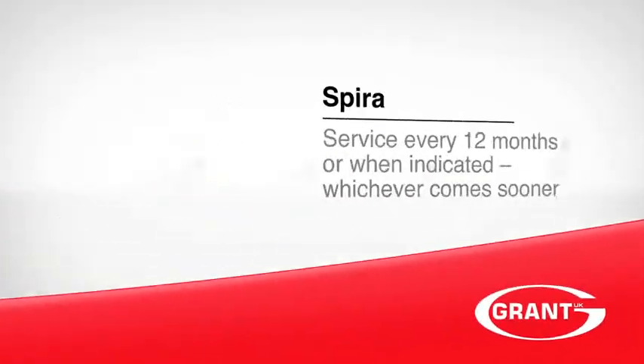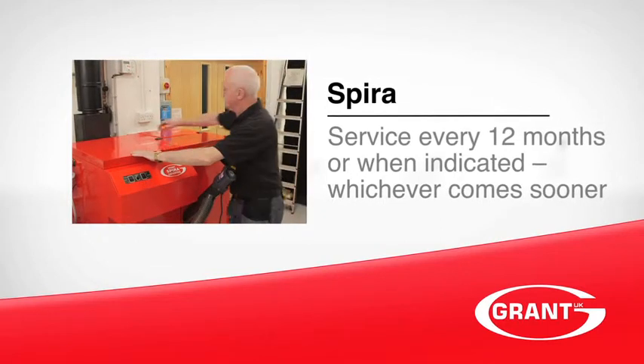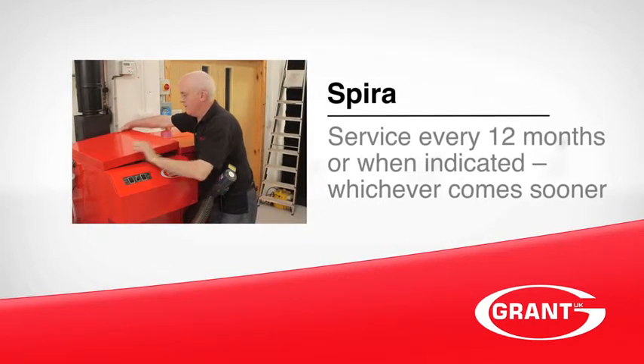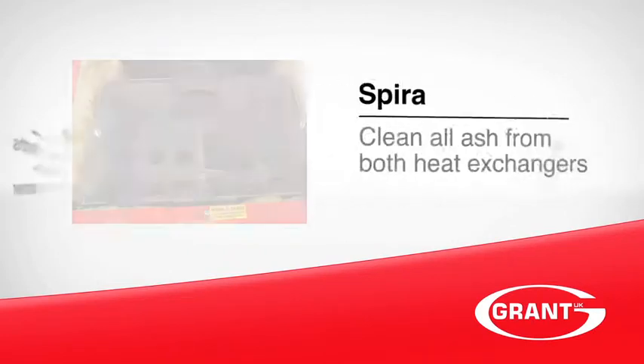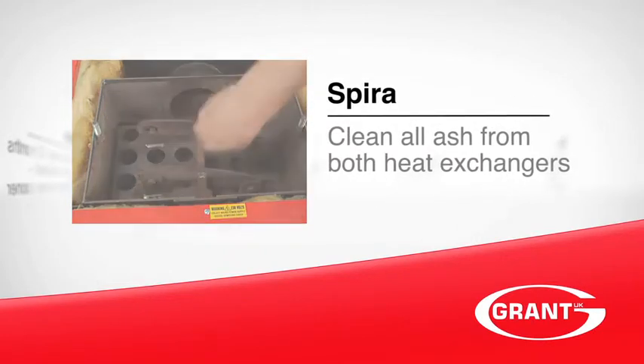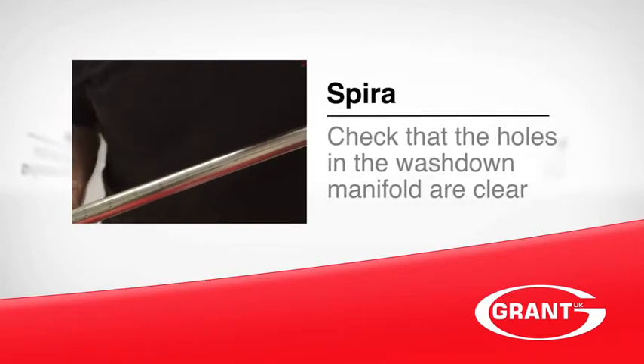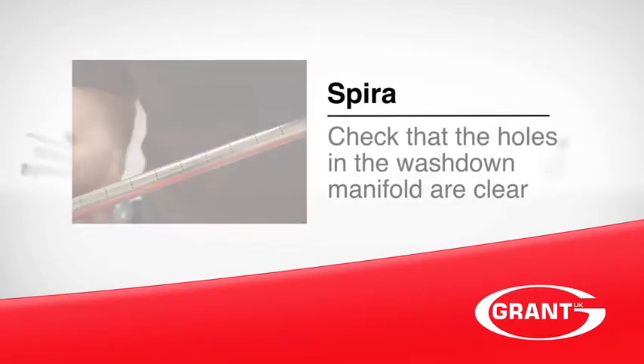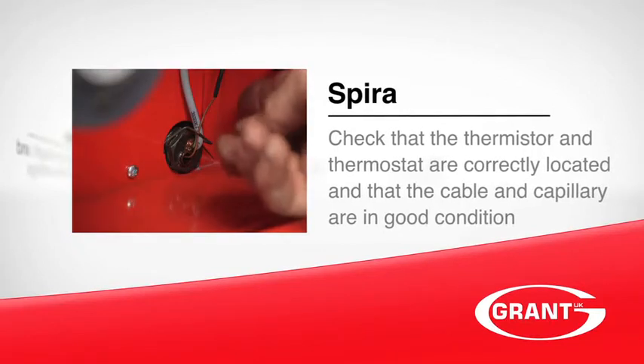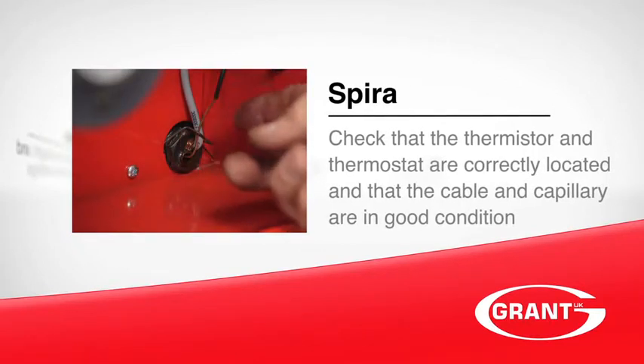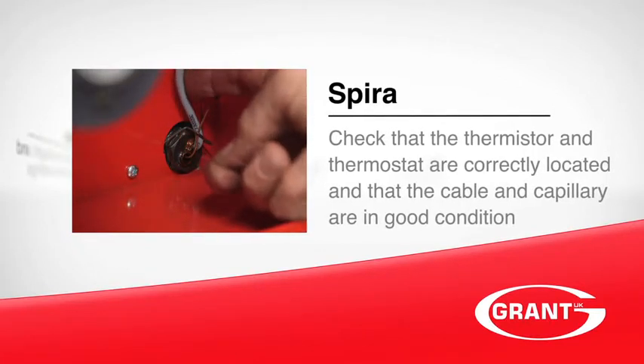So remember, the Grant Spira biomass boiler should be serviced when indicated on the burner display or after 12 months, whichever comes sooner. Clean all ash from both heat exchangers. Check that the holes in the washdown manifold are clear. Check that the thermistor and thermostat are correctly located and that the cable and capillary are in good condition.